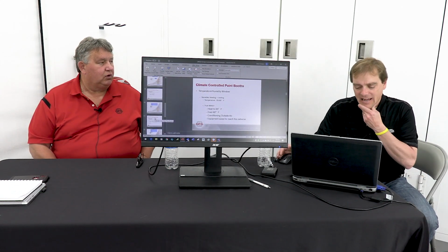All right, next question we had was, how is humidity measured in the booth, and what is the typical tolerance range? So the type of sensors used typically are fixed sensors that can be mounted right in the system. It could be mounted in the paint booth or in the makeup air supply ductwork or exhaust ductwork. That's typically what we do in a climate controlled booth. We have those sensors, so they're fixed, and they're rated for the environment in which they're located, which could be a class 1 div 1 area, explosion proof area. So they're rated for the environment, and they have accuracies of plus or minus 2% typically.